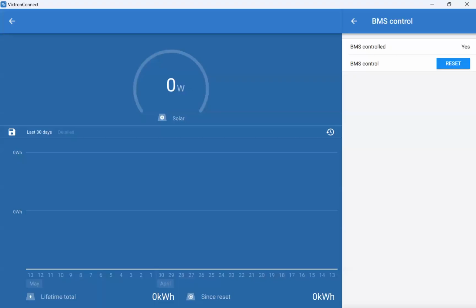Yes, I'm going to reset it. And it says no for a while. Then it will come back and click onto yes as soon as it sees data coming from the BMS again. It may take seconds or it may take up to a minute. But there we go, it sees a BMS. It's going to now revert to whatever the BMS is saying and not its own programming.